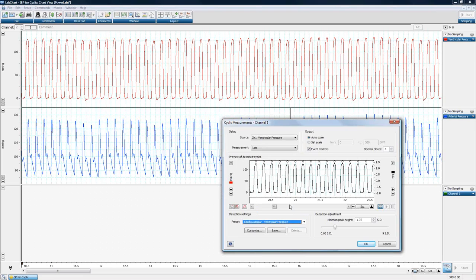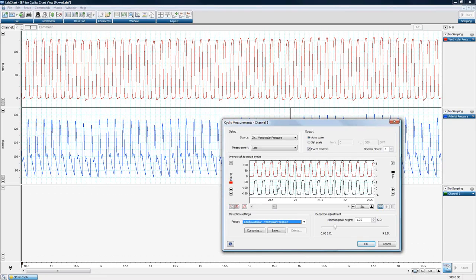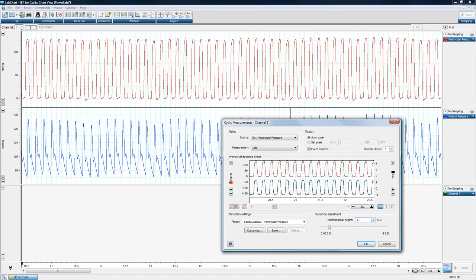For a ventricular pressure signal, selecting the 'Cardiovascular Ventricular Pressure' preset works best. The sine wave preset also does a reasonable job but the cardiovascular preset handles amplitude variations better. The Minimum Peak Height setting — expressed in standard deviation when using normalization pre-processing, or in raw units for simple threshold — controls how high a peak must be to be detected. Adjusting it up loses some beats; adjusting it down recovers them.